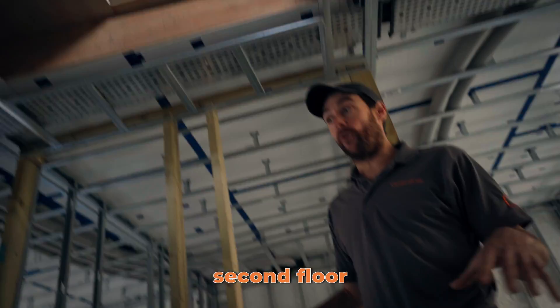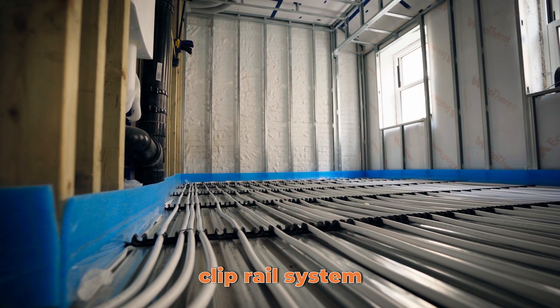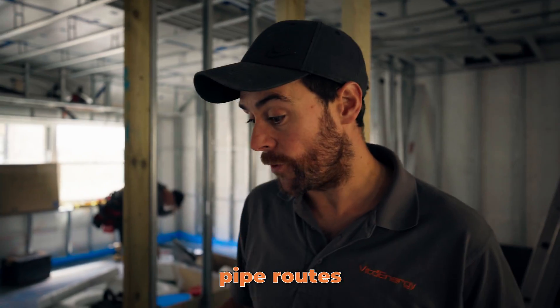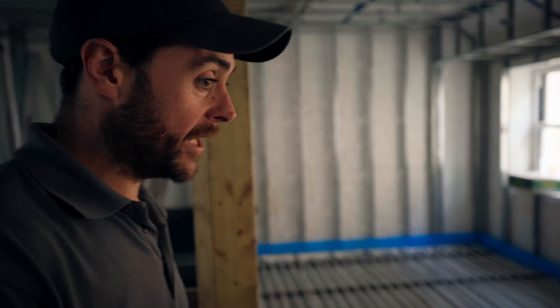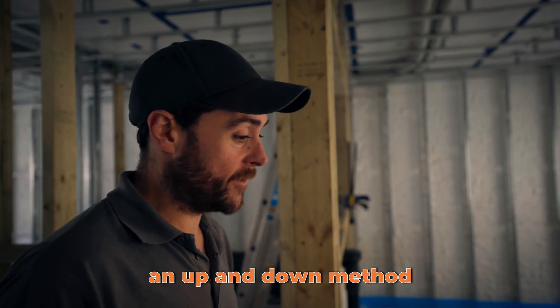Into the second floor of the property, we've got a slightly different setup up here. We've got a more commercial-style Lewis deck floor that's gone down, and we've got a clip rail system going in for the underfloor heating. A little bit of thought required here to make sure we've got the exact pipe routes in and out of each area. Back to our manifold — up here it's a nine-port manifold with 16mm diameter pipe and again 100mm pipe centres. Because of the nature of the layout, we've had to go for an up-and-down method as opposed to a snail.